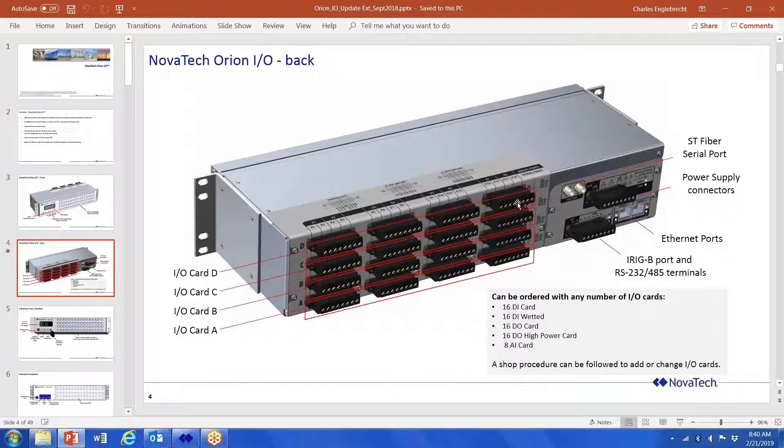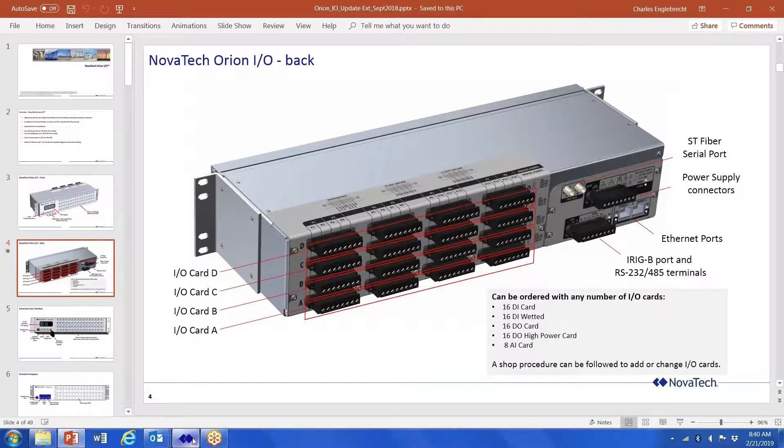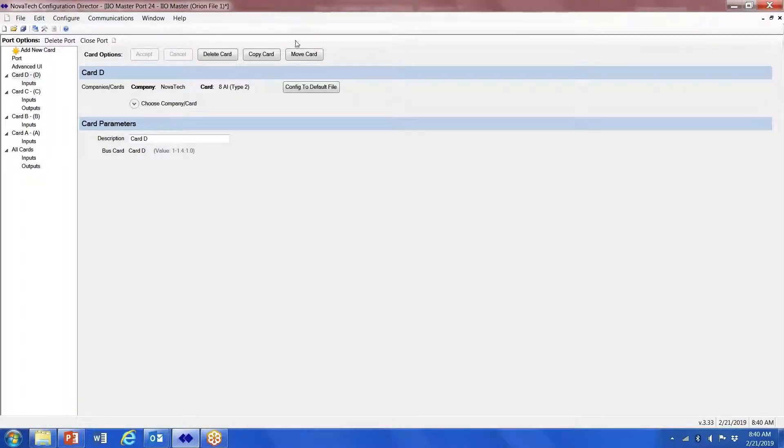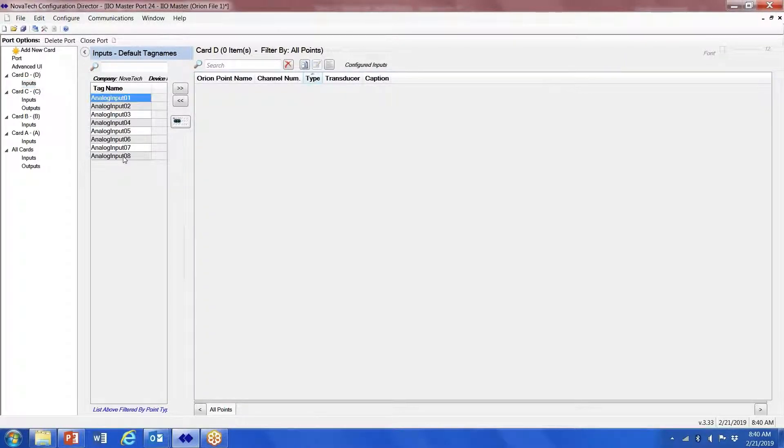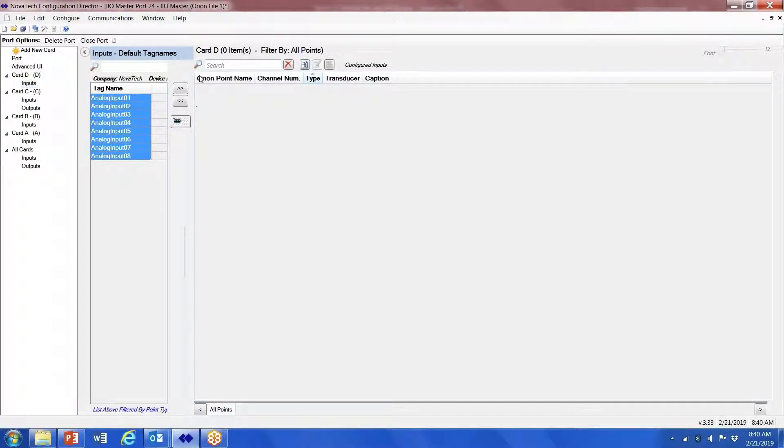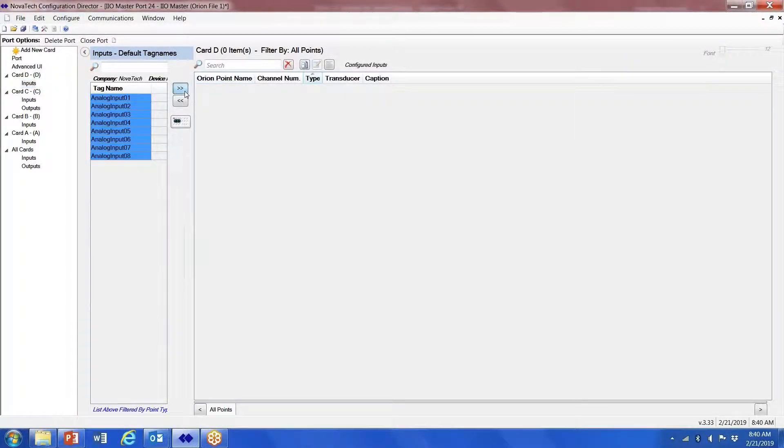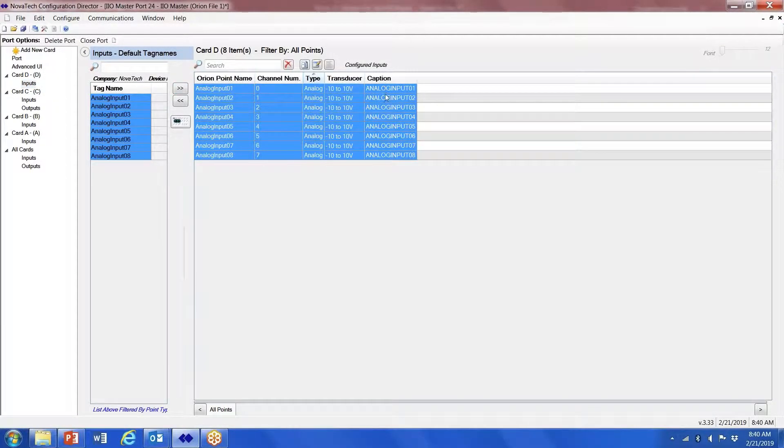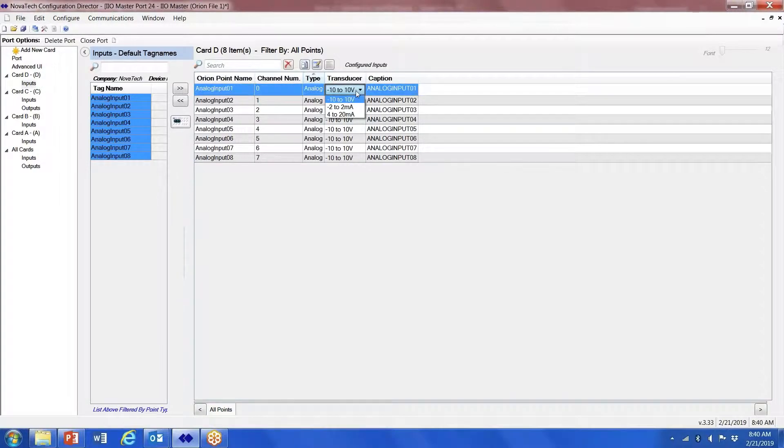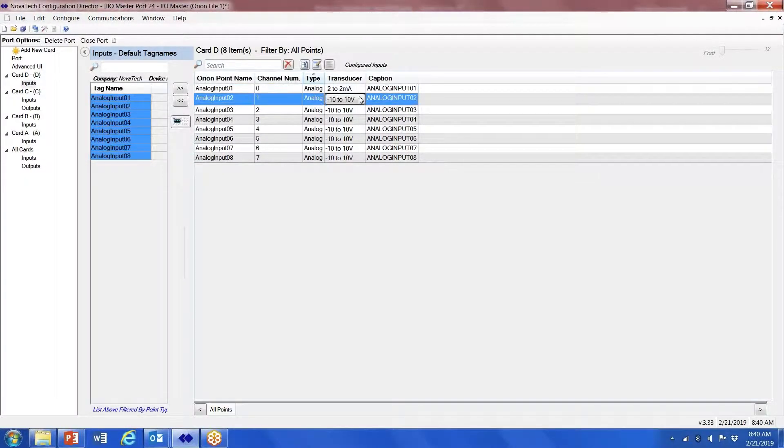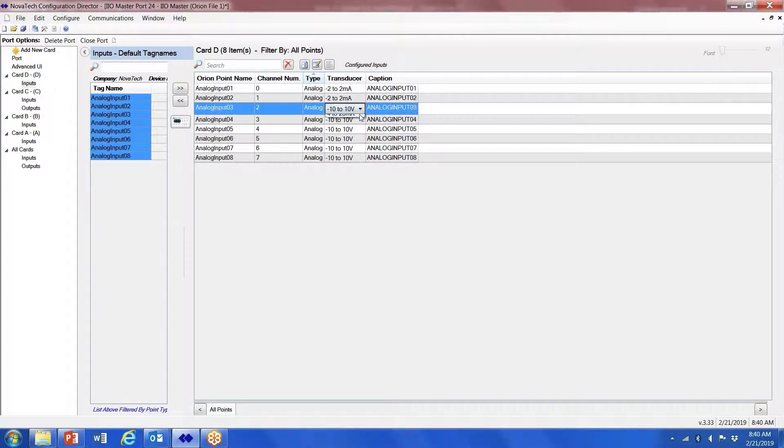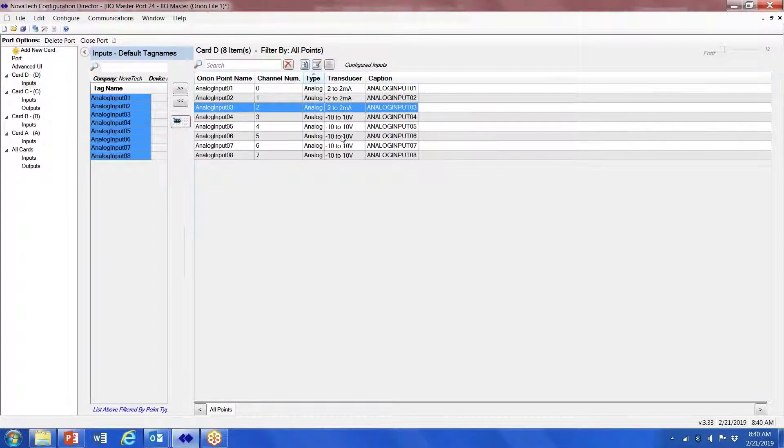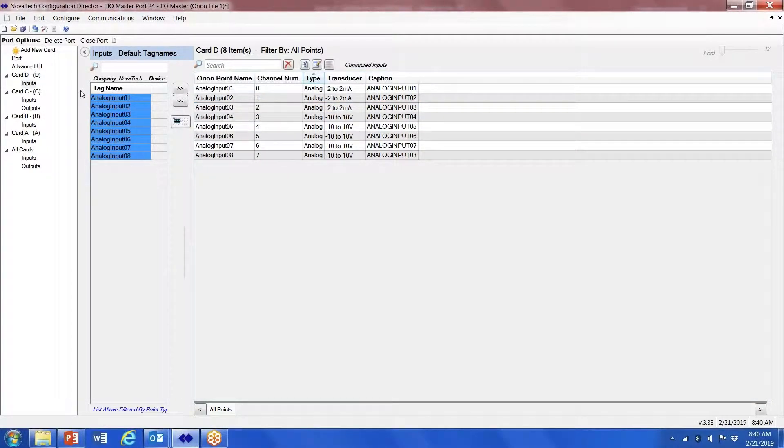Once I know how my termination is set up, I can go in and click on my inputs, map over my analog points, change my caption that I want here—low pressure gas, SF6, etc.—and then select how I've wired up my inputs here.